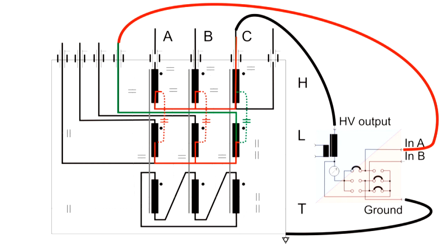If the connectors of the high-voltage bushings and the low-voltage bushings are not connected to each other, current also flows through a second winding. As a result, the core gets magnetized, leading to further losses, which overlay the dielectric losses. These additional losses can create conspicuous effects.